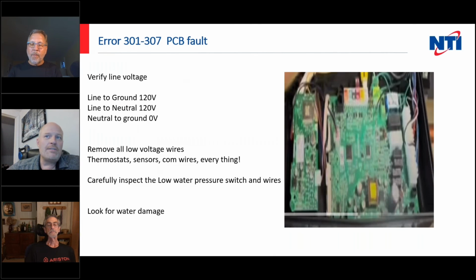So 301 to 307, this is like an internal PCB fault. Any internal fault on any boiler from any manufacturer, you should always start by doing the same couple of things. First thing you're going to want to do is line to ground, line to neutral, neutral to ground. If you do not get these readings, or like 110, 115 volts, and you get like 50 volts to ground on neutral or something, fix your power first.